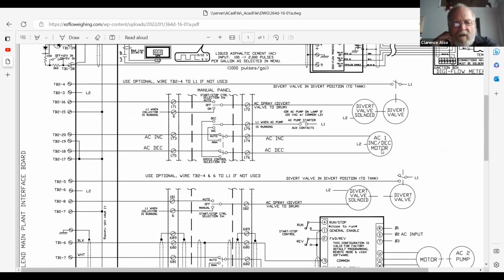Okay, here's our divert solenoid. Then look at the divert valve, and that's got a little limit switch tied to the back of it. Bet that little yellow limit switch goes to a yellow block, telling you that we're actually closed. Black one to the solenoid there, TB2-16 - this guy right here. That's gonna come from a black block and say, okay, open that thing up. Then the valve opens up, the switch goes back and it's on to the yellow one - the yellow one's red light comes on and says, okay, that switch. So that's what you're looking at.